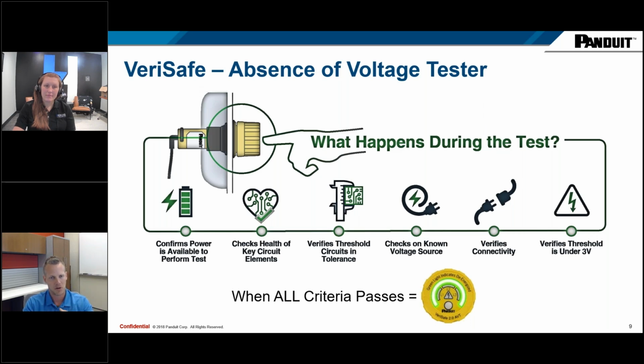Then it checks the known voltage source. It verifies that it's connected properly. If it is, it then verifies that the threshold that it measured is under 3 volts. And then it goes through and does that whole set of tests again. The only way you will get a green light is if it passes all 6 of those tests twice. If it fails any one of them, it fails the entire test and will not give you a green light. That's where we get that SIL3 rating. If you have a manufacturing issue and a resistor or a microcontroller inside the device fails, it's going to fail that check of the health of key circuit elements. At that point it fails and it's not going to give you a green light.